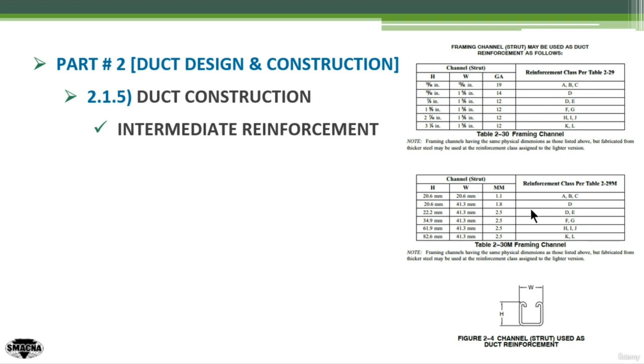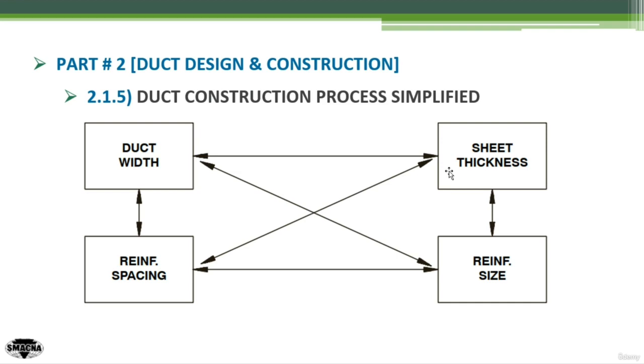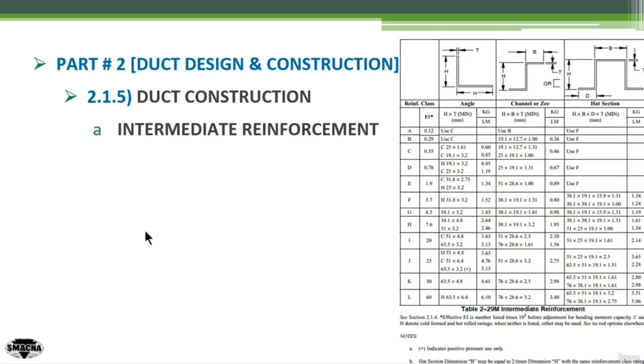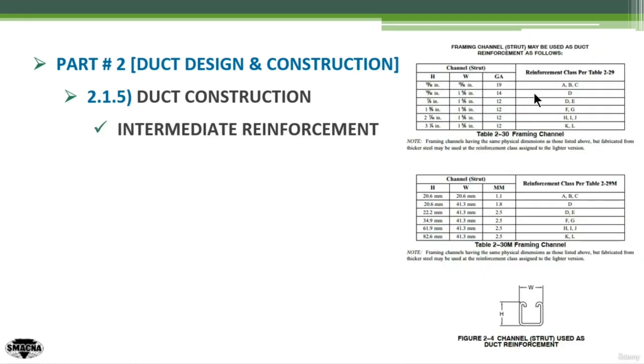We can see this table in both mm and inch units — SI and British units. For the slotted channel, you have three inputs: the height, the width, and the gauge of the channel. Based on the reinforcement class, you can obtain from the earlier tables the reinforcement requirement based on the pressure classification. Going back to those tables, you can have reinforcement classifications C, B, E, D, F, etc. This denotes the reinforcement classification for the slotted channels, and we can use it as the entry point to get the dimensions of the slotted channel or the framing channel.